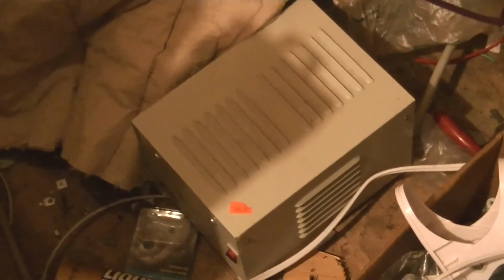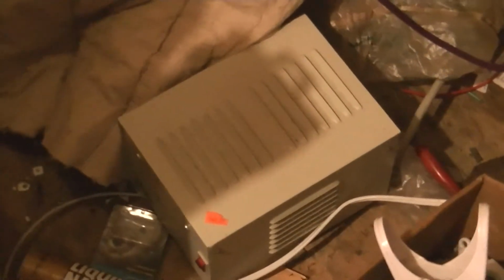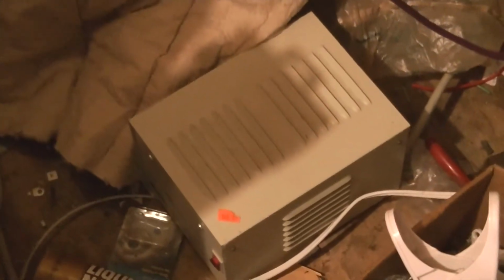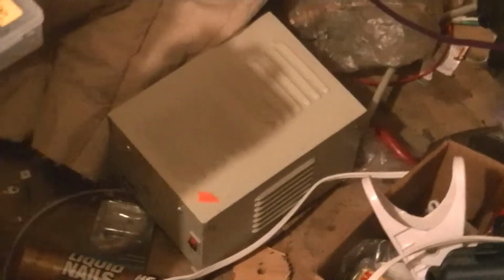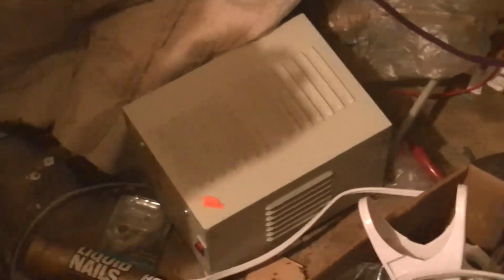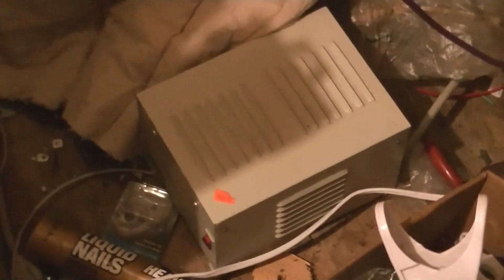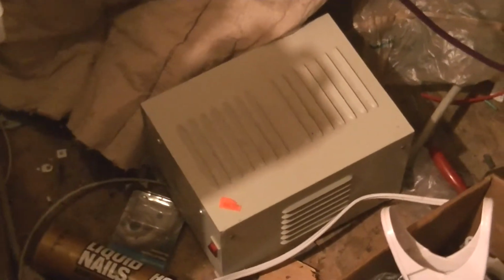And I also have this guy, which is an 800 volt ampere conventional interference limiting isolation transformer, although these, when you buy them, the neutral is electrically grounded in the transformer on the secondary side. So I simply broke that connection to make this a true isolating transformer. I think I've covered this in a video a couple of years ago when I got this, and another one because I have a total of 2 of these. This particular guy is just serving as an interference limiter whatchamajig for this Cotek pure sine wave inverter.